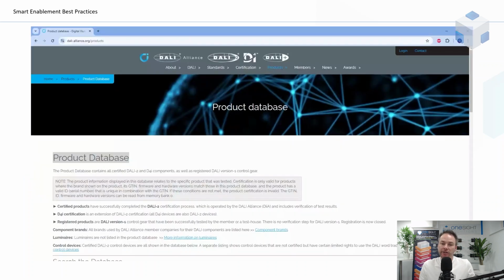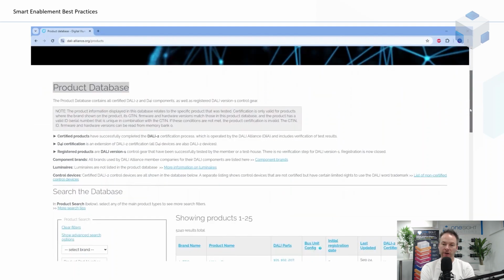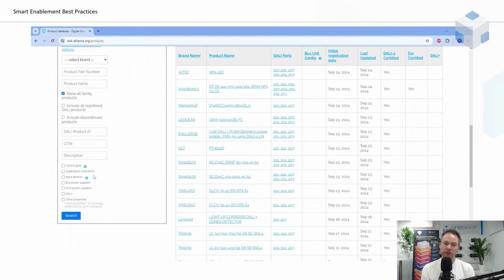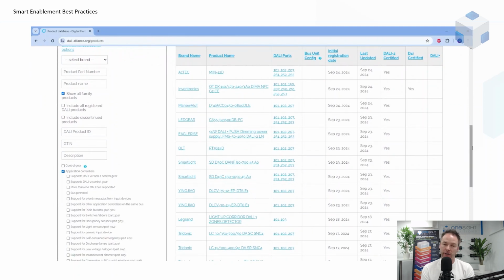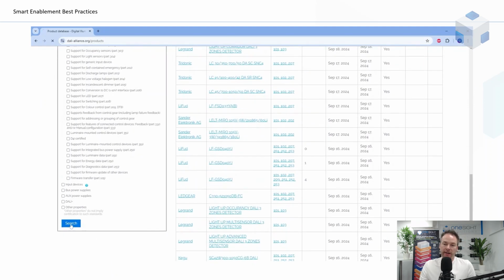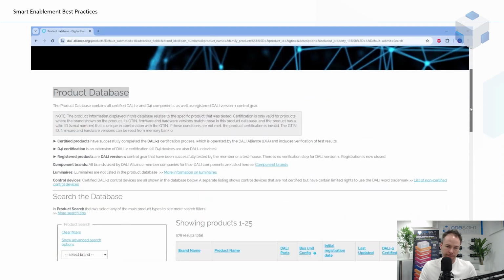I won't go into the nitty-gritty of DALI too much, but a DALI application controller is the device at the centre of a DALI system that orchestrates the commands out to the DALI light fittings. It tells them to do their monthly test, reads back the battery charge, etc. On screen now is a list of all the certified DALI products, which you can see on the DALI Alliance website if you wish - there are over 5,000 of them currently. If we take a look at the list of certified application controllers though, we can see there are around 678 of them at this present time.